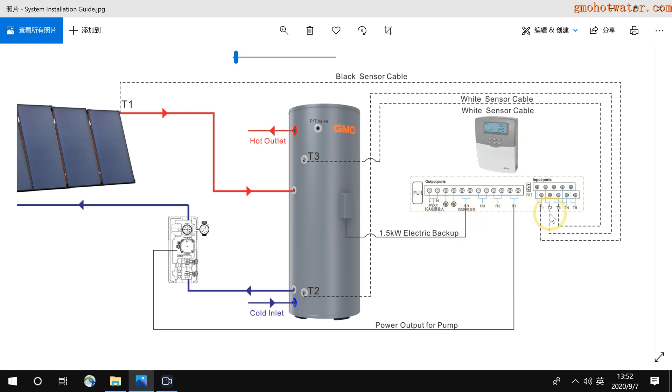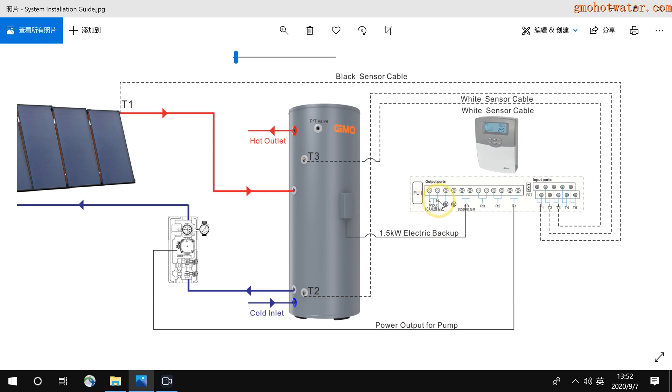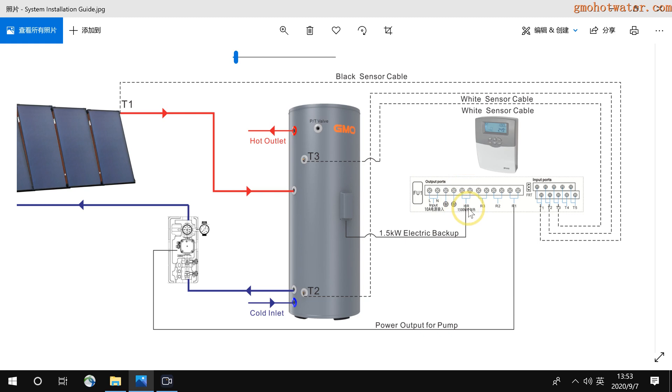From the left to the right, it is the power input. This is the power for the controller, and also it will give power to the pump. Live wire, zero wire, and here is the ground wire terminal for the power input. And also the HR is the electric backup. Here, the ground wire terminal can be used for the electric backup. The maximum power is 1500 watts. So the tank is with a 1500 watt heating element. You can connect to here.